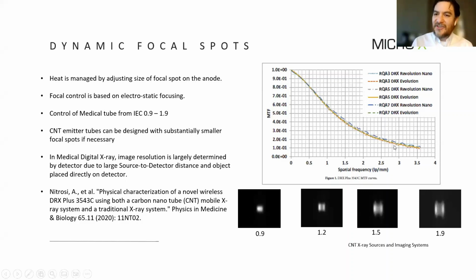And there was some interesting work done. There's a reference here where one of our mobile systems was compared to a conventional mobile system using the same detector, and the measured MTF was identical despite the difference in focal spot size. And that's because of the source to detector distance. So by changing the focal spot, we can take advantage of that to manage the heat in this application. However, the same physics, and we've demonstrated this, we could make a substantially smaller focal spot when the application calls for it. There's no fundamental limit that says it can only be a 0.9 focal spot. We could make a much smaller focal spot if the situation called for it. It's really a balance of the heat on the anode and the size of the focal spot we want and the current that we're running at.